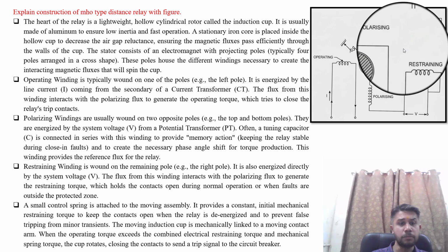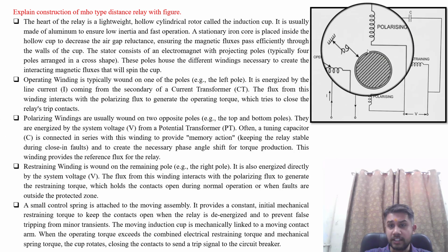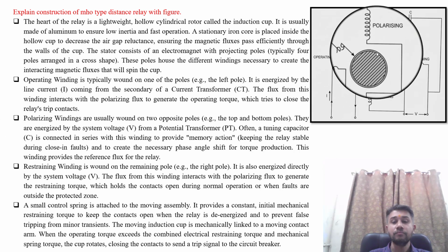A small control spring, which is made of phosphorus bronze, is attached to the moving assembly. It provides a constant initial mechanical restraining torque to keep the contacts open when the relay is de-energized and to prevent false tripping from minor transients. The moving induction cup is mechanically linked here to a moving contact. Here you can visualize this. It is connected with the moving arm, or say moving assembly.